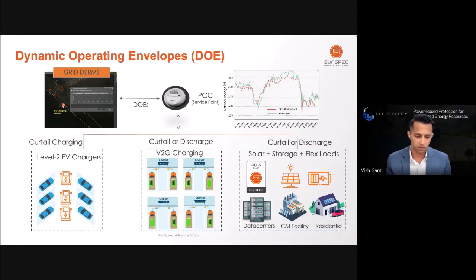Historically, getting these interconnection permits takes a very long time, especially if you're in the megawatt order - it takes 2 to 3 years. This has been a key bottleneck that flexible service connections are trying to address, so that we can bring load faster, with energy available to those sites under certain operational characteristics or conditions.